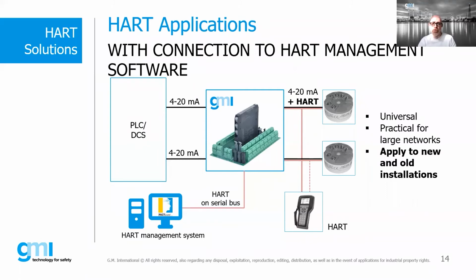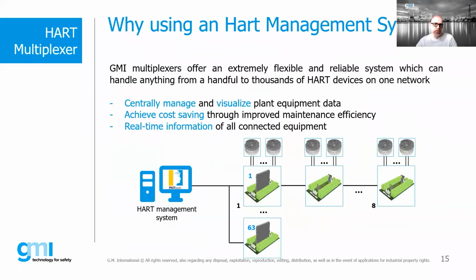Thanks to the management of up to 256 channels per card, with communication speed up to 1,200 bps. The HART protocol is also fully supported by custom I/O termination cards, by D5000 barriers, and by D6000 isolators. The use of a HART multiplexer offers different advantages, and it's necessary when the PLC or DCS don't integrate the HART modules. The HART multiplexer can be integrated in an existing system where transmitters, modules, are transparent, are connected.